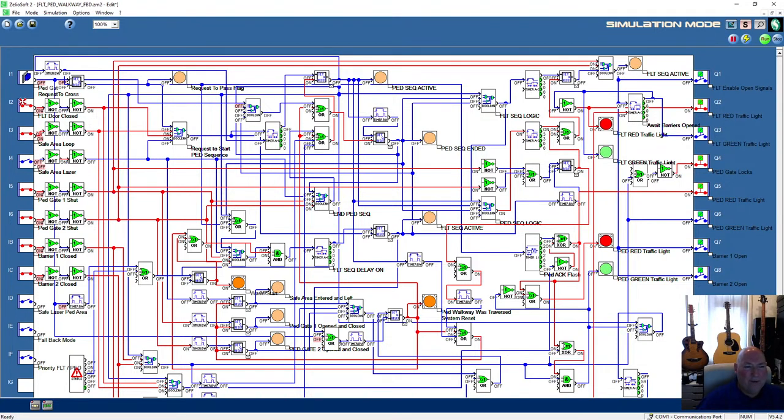So if the barriers are out of commission, the roller shutter door's out of commission, or they're holding the roller shutter door up because it's red hot, it's in the summer, and they're going to have the door open for whatever reason, or it's been smashed or broken, or the boom has been knocked off and the barriers have been switched off, anything like that, you still got to use it as a normal pedestrian walkway. So what we'd have to do, instead of this switch, we'd have to satisfy certain criteria at certain times to be able to let the rest of the system function. So we'd have to work that out after. We can see what we're waiting for. So with this switch, we'd have to activate some kind of logic with more than one output to override certain parts of the system.